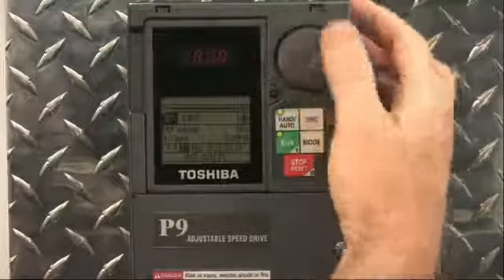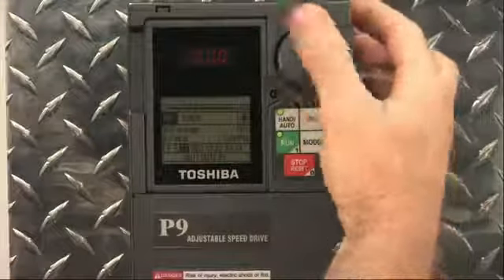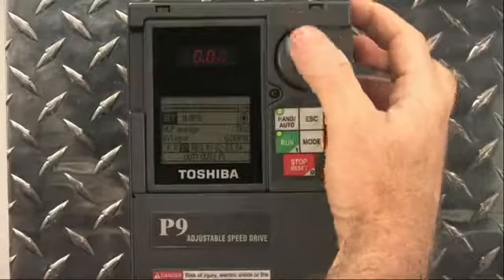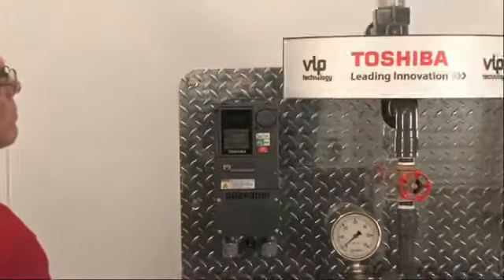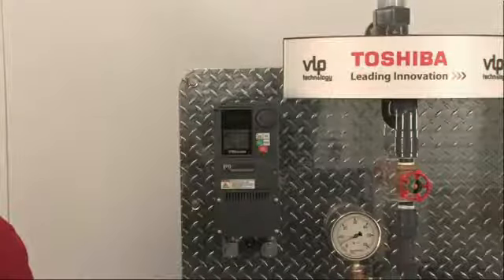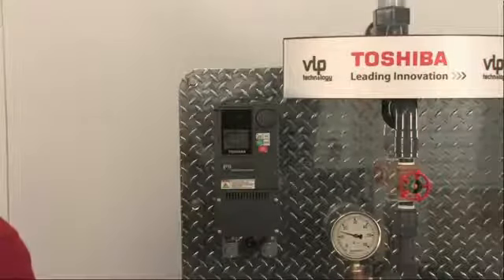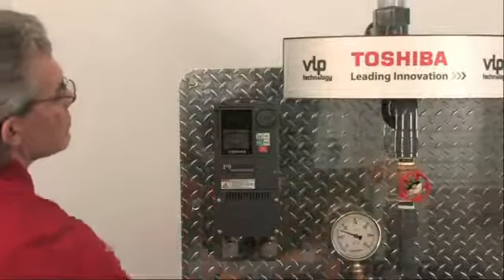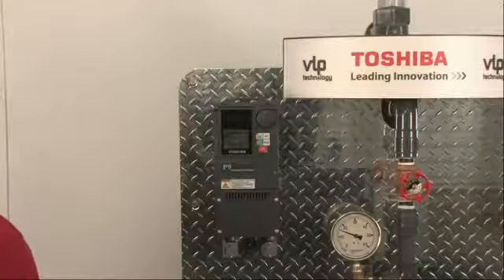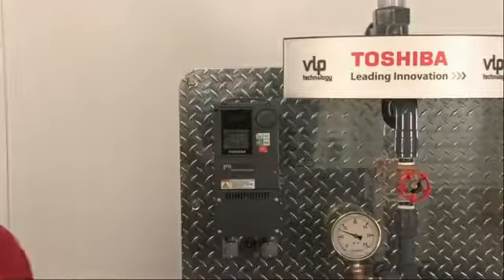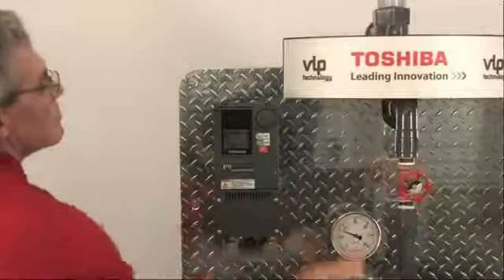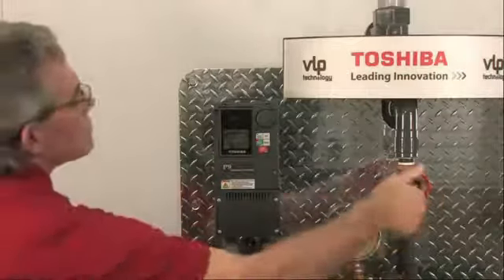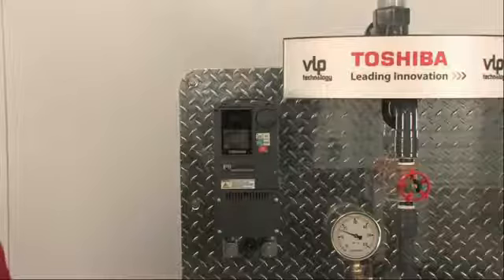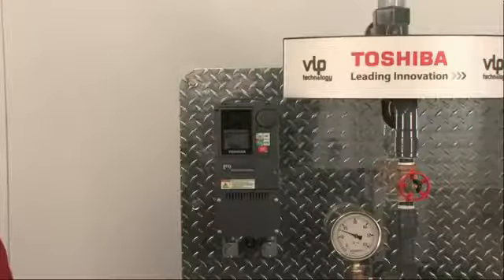Using the encoder, we raise this set value to 15 PSI and press Run. The pump will start and accelerate until the process pressure is 15 PSI. If we open and close our throttle valve, simulating system transients, the drive will automatically adjust its output to maintain system pressure. If we adjust the set point, the drive will automatically adjust to maintain system pressure to the set point we programmed into the P9. As we simulate these transients, notice the VLP number on the second monitored item. This number will vary based upon the mass flow of the system. This is the fundamental difference between a PID control loop and VLP process control. VLP monitors and controls mass flow, whereas PID is simply speed control.